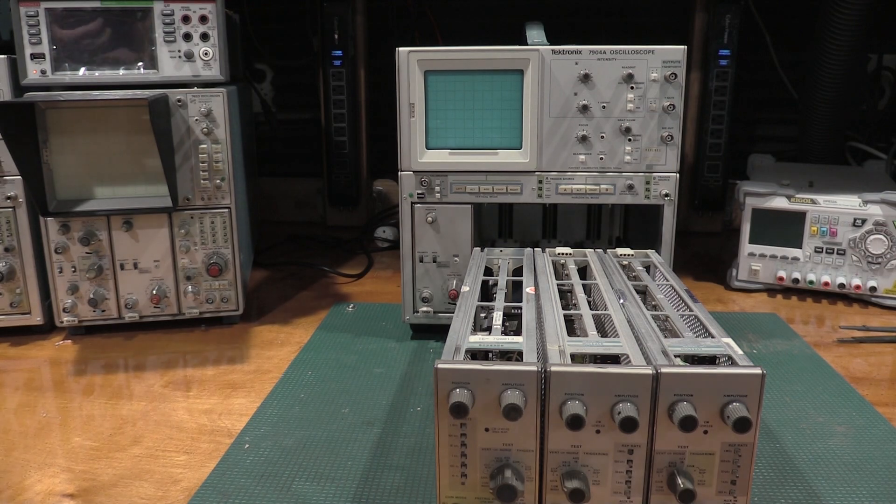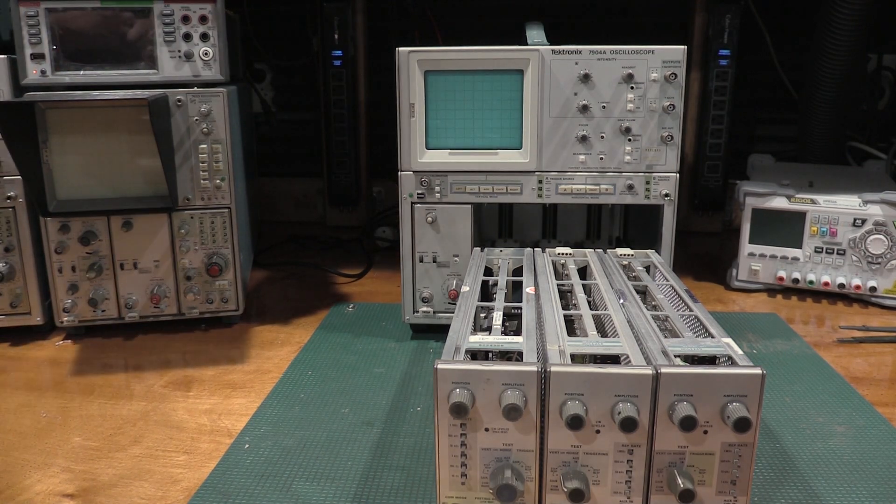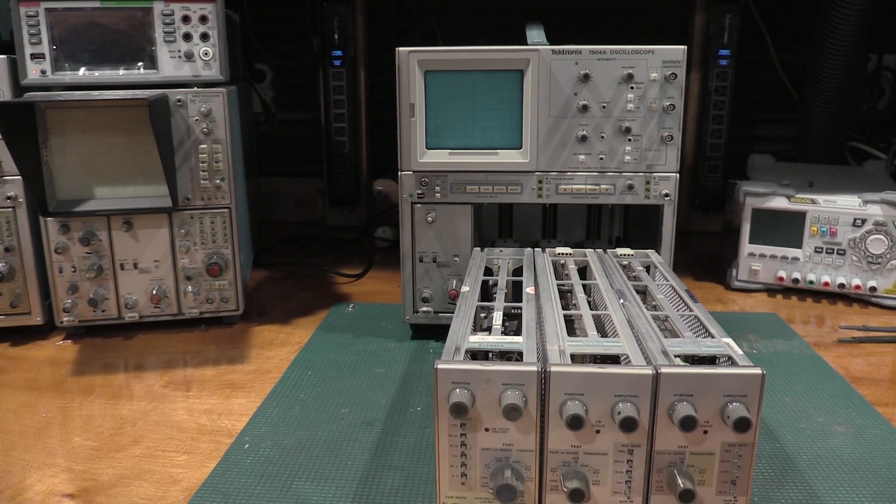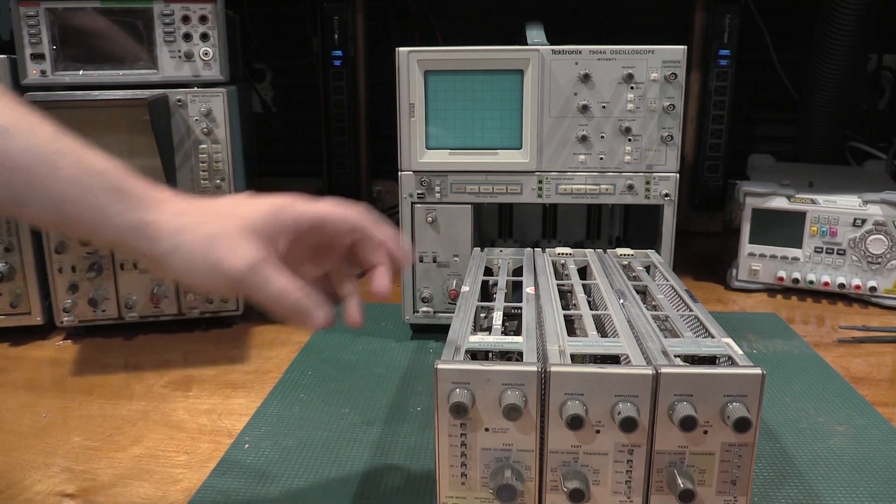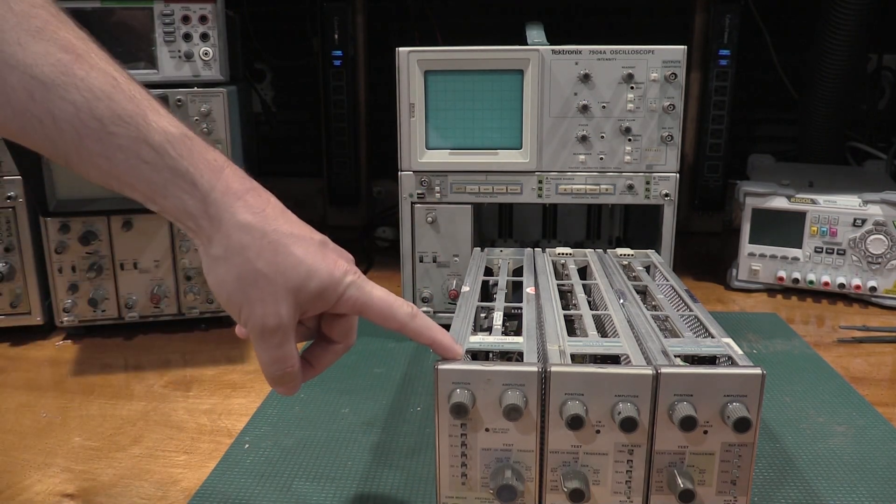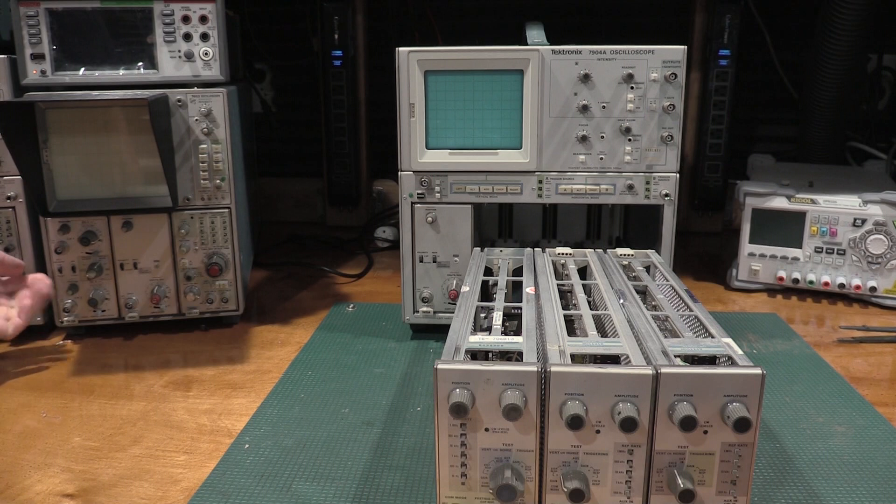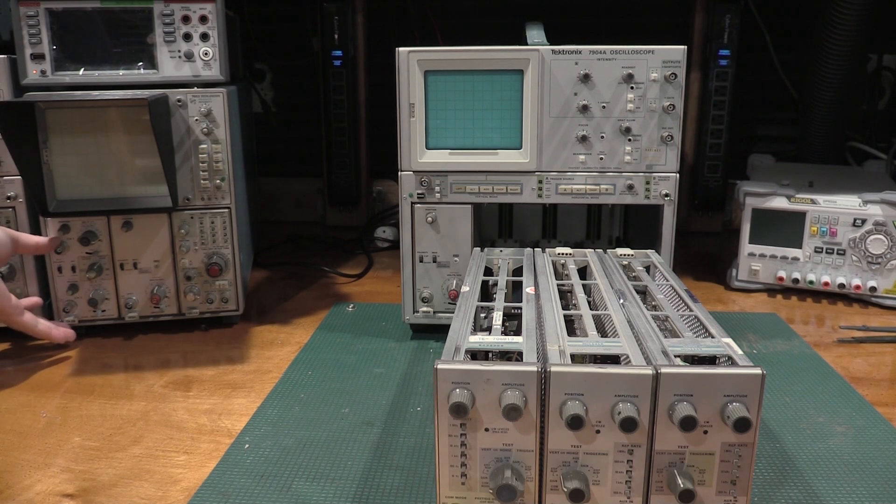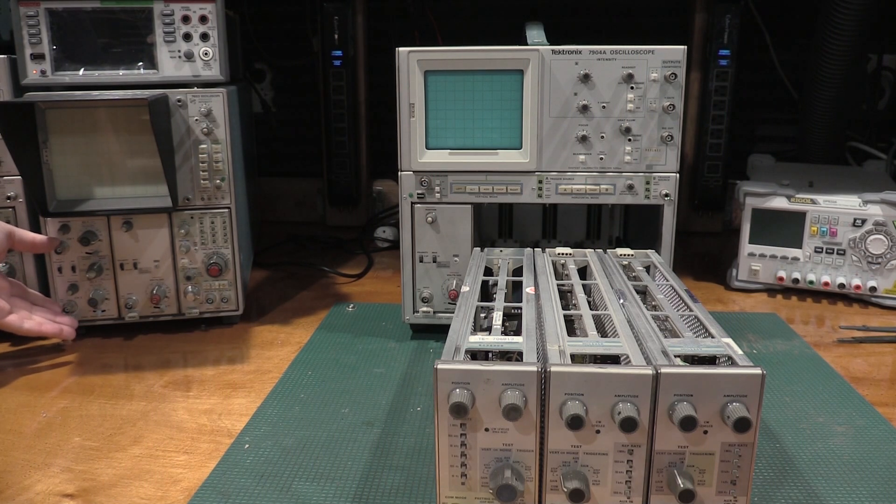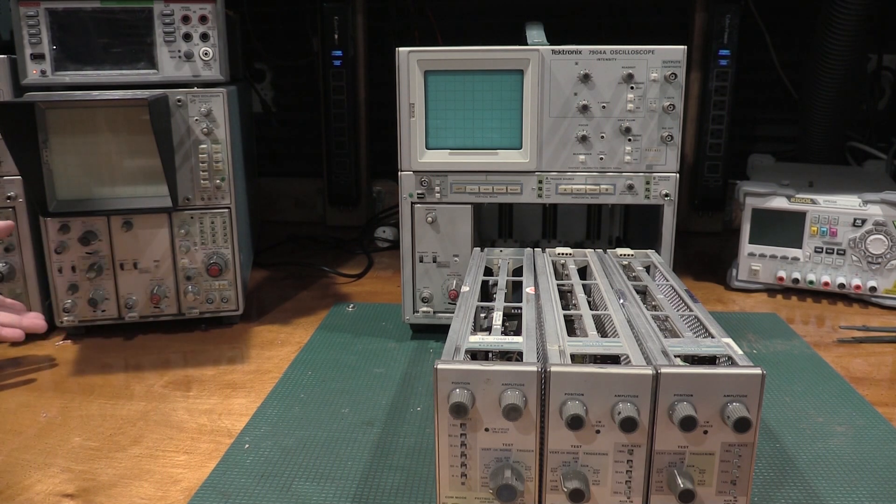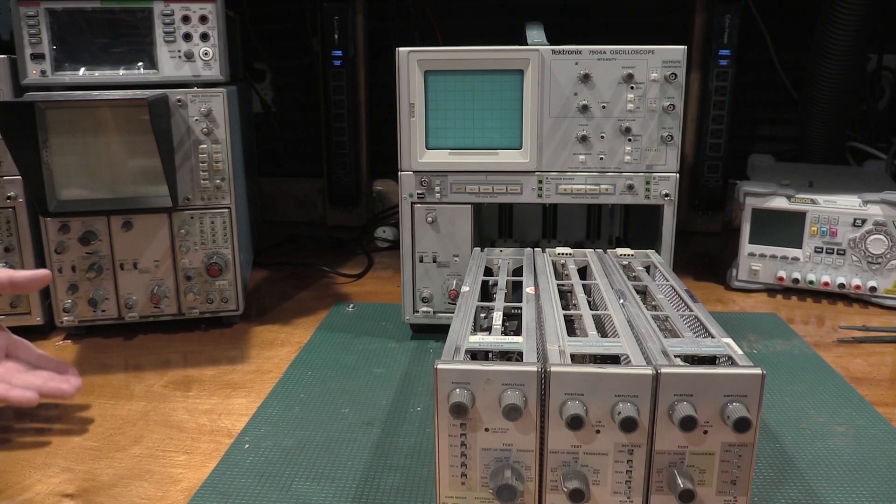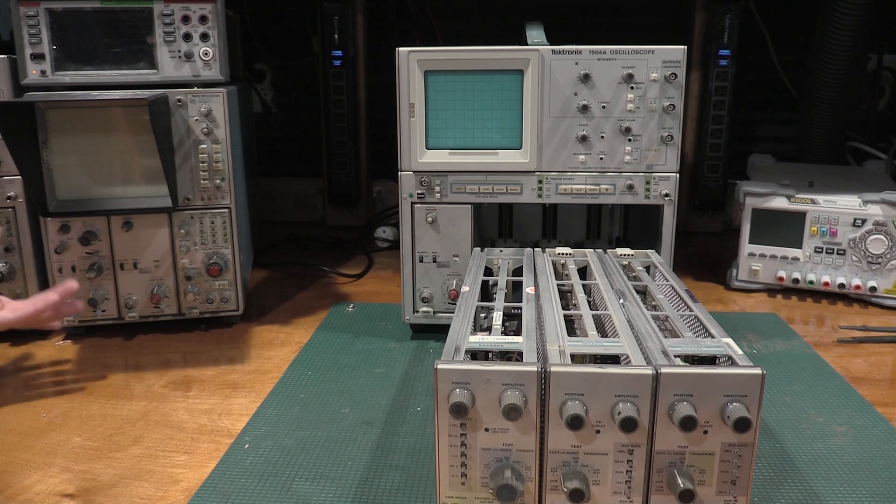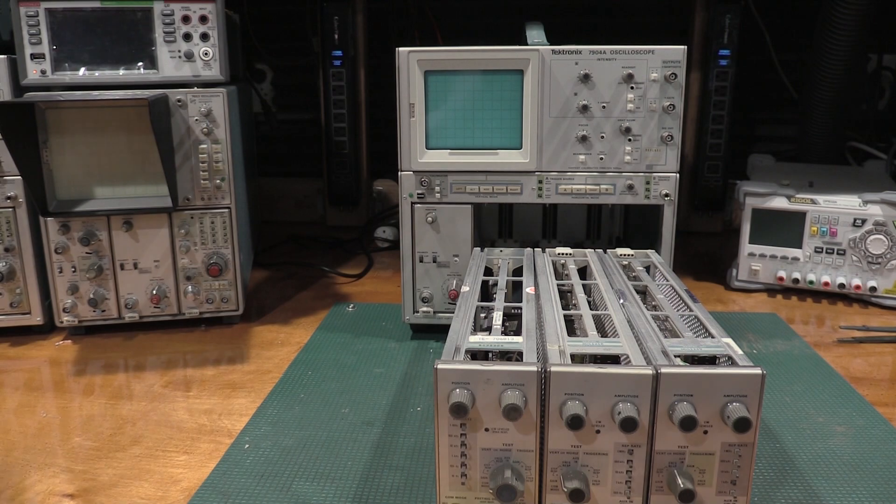And a lot of the manuals, especially some of the 76 series call that out. They say, yeah, it's perfectly okay. You do not need one of these signal standardizers to do an alignment, but don't move the plug-ins after that. Align it with those plug-ins and then lock them in there and leave it and consider it a unit.